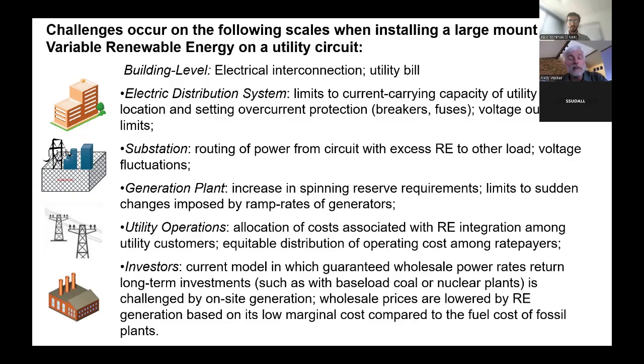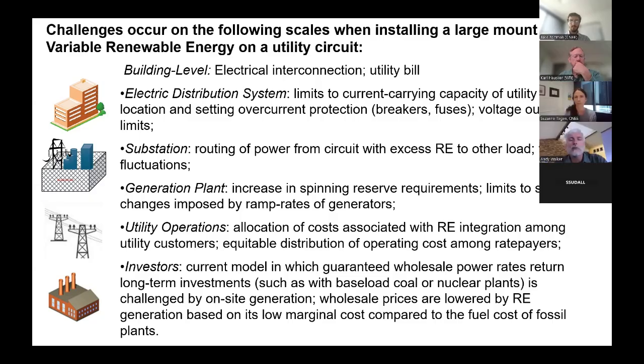Another topic Mayor Udall put his finger on is the ramp rates: how quickly can I ramp up a generator to meet a sudden decrease in the wind or solar resource? A third parameter is how low can I turn down the conventional coal-fired generator when the wind or solar is at a maximum. There's usually a minimum turn-down ratio, and we have to operate within all three of those limits.